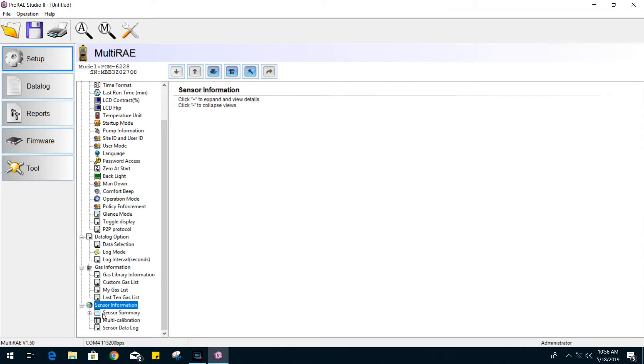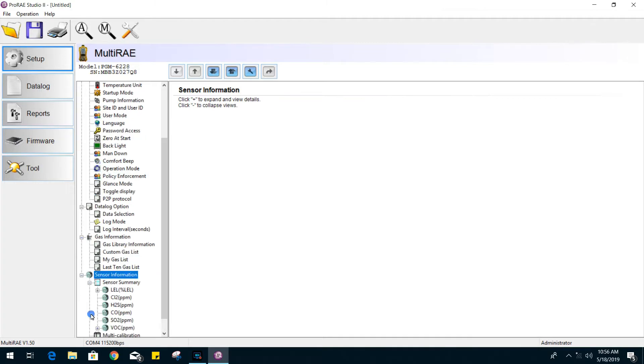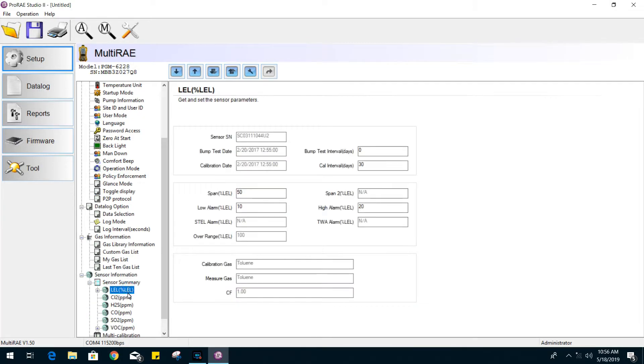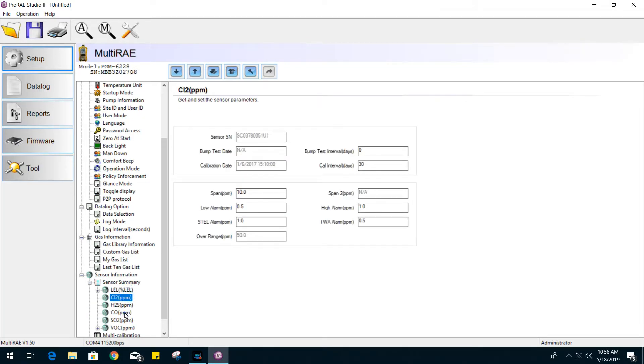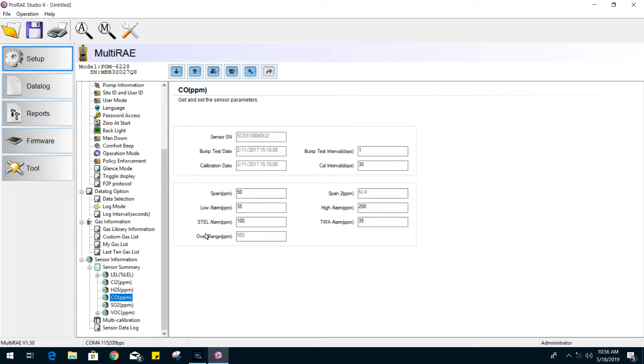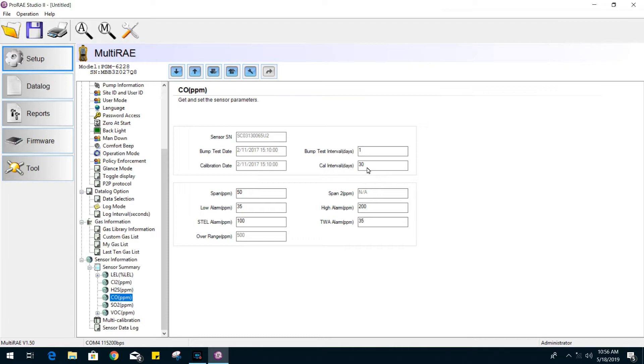Under sensor information, you can go to each individual sensor. You can change the settings like the span value for calibrating your sensor. We have the low and high alarm set points. The STEL and TWA can be modified as well. You can set the cal intervals for the calibration frequency at your unit. You can also set the number of days for your next bump test.